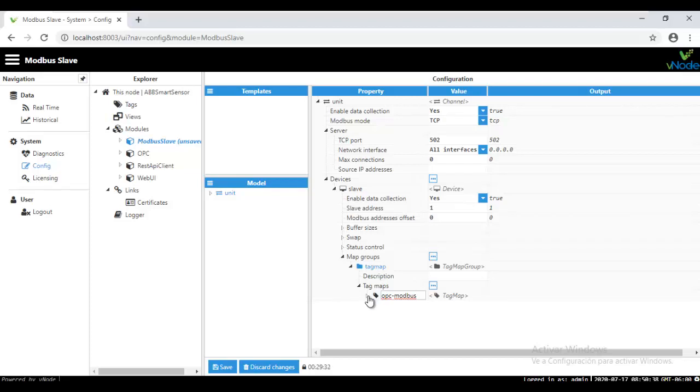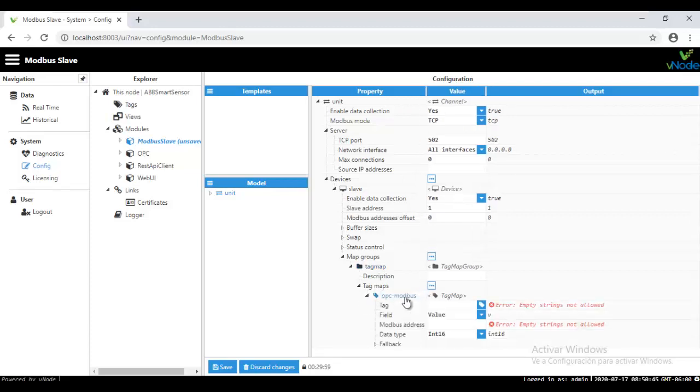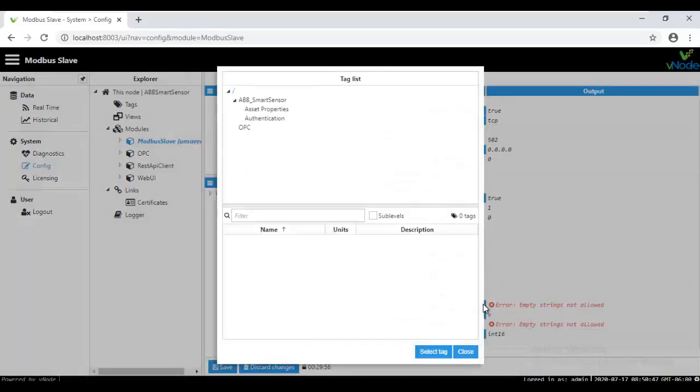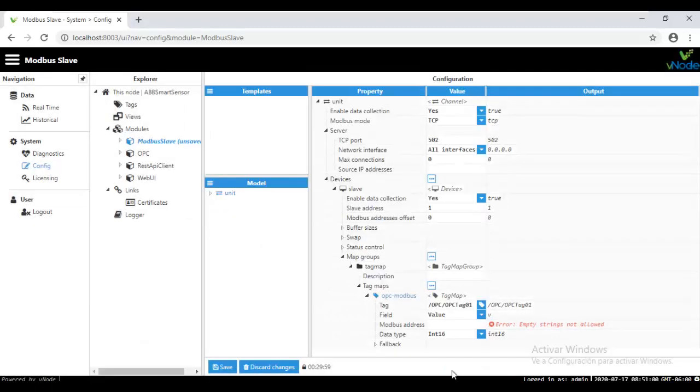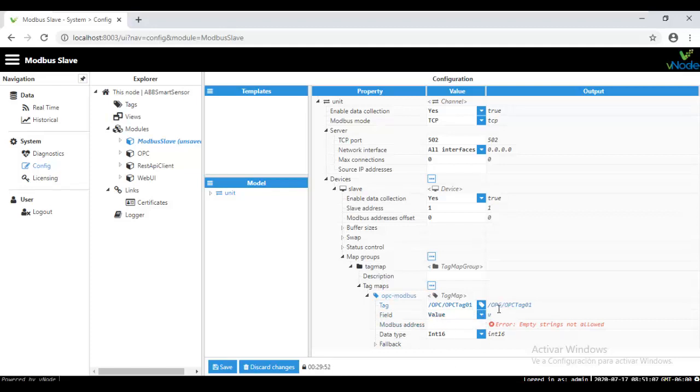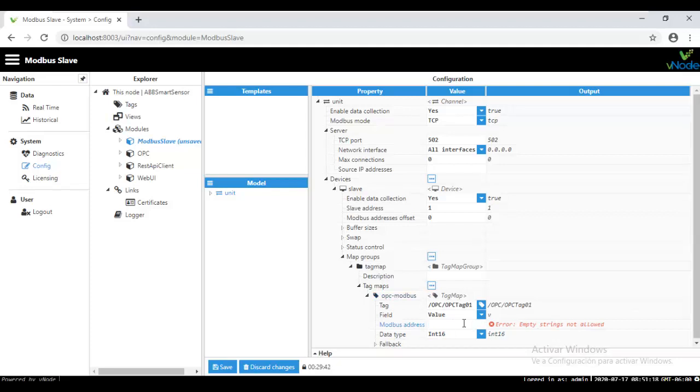So under tag, you are going to select the tag, in this case that will be mapped to Modbus address. So I have already created an OPC tag right here that is coming from other environment. And then I'm going to map the value, the value of the tag, which means that I'm going to see the same value in Modbus address. Data type, it will be Int16. And also the Modbus address we need to use is the one that we are going to choose in this case. I'm going to use like holding register. So I'm going to use the 40s. And hit on Save. If everything is okay, we need to start testing it, the full solution with the Modbus master.